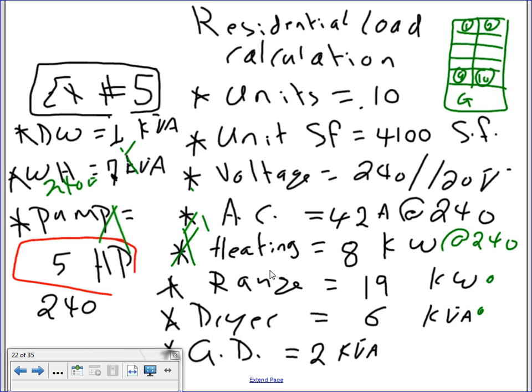Okay, now the next thing, guys, I want to do is find a neutral. I want to remind you for the neutral, anything that's 240 will be dropped. For example, this load here will be dropped from the neutral. The pump will be dropped. The AC will be dropped. The heating will be dropped. The range and the dryer, we take 70% of these, right? Anything 240 will be dropped.